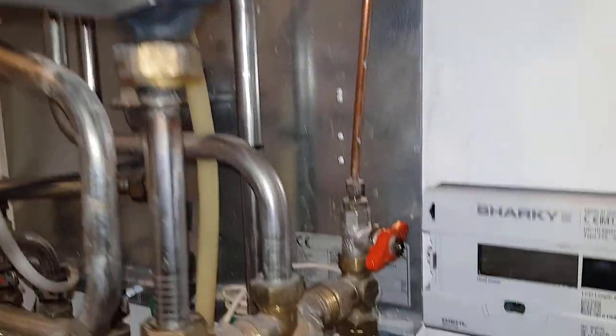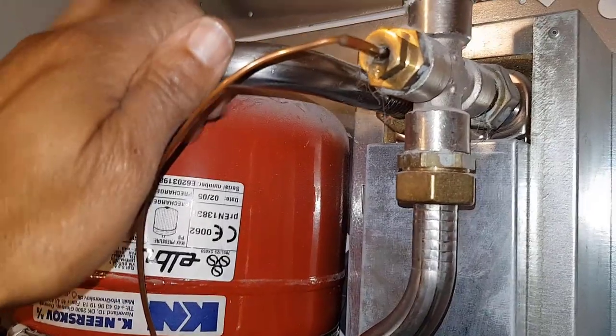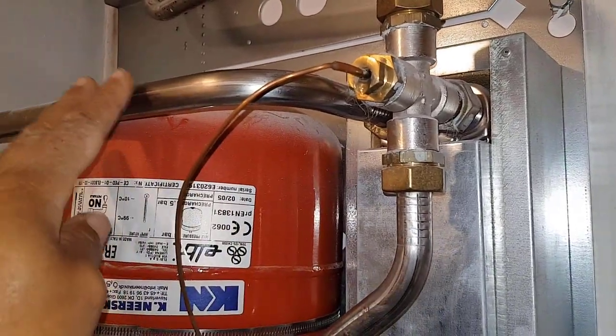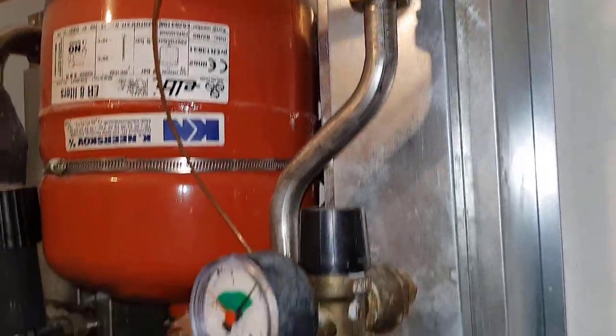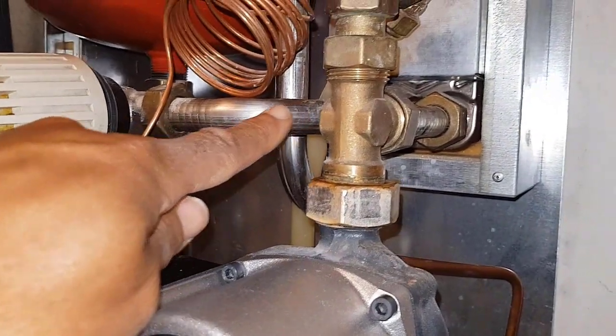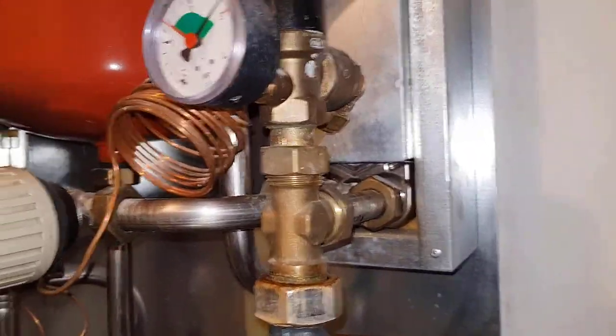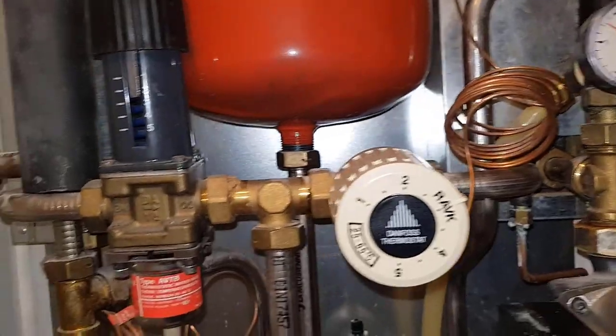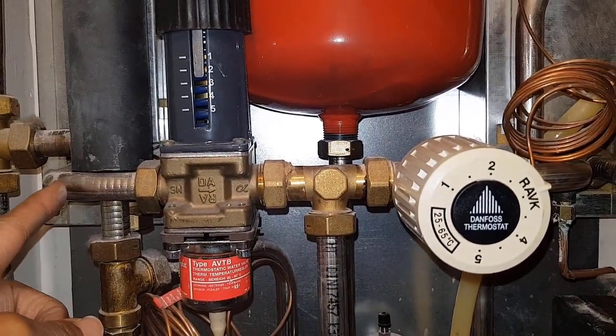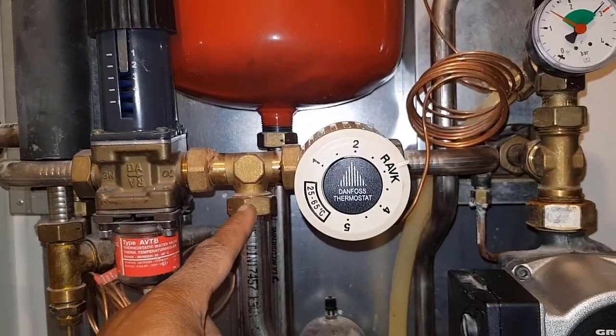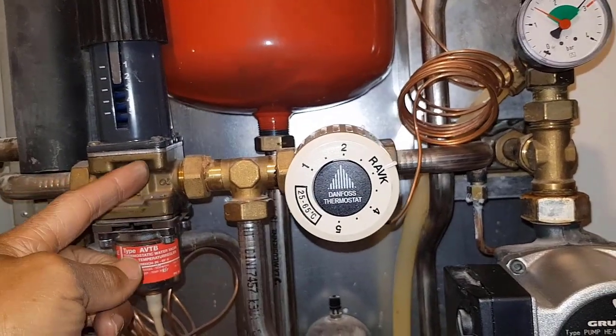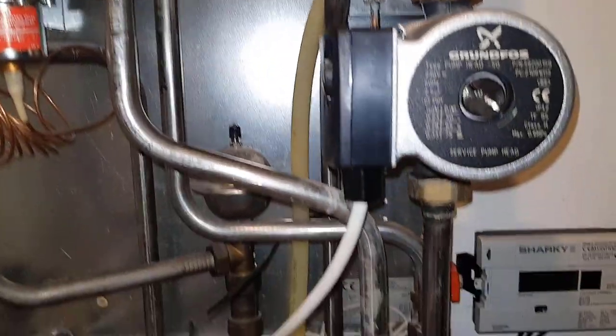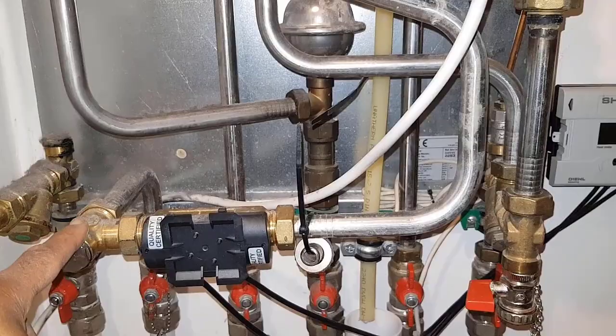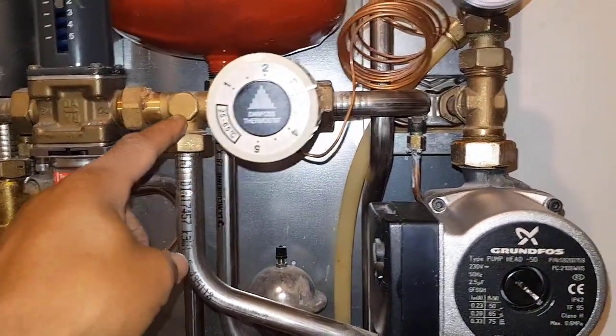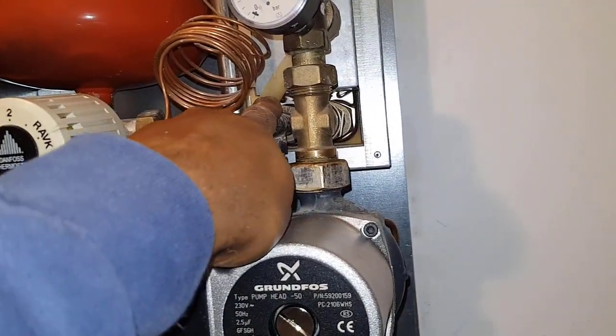What I've done now is open this bypass valve here, and what we've now got is this has got really hot. That's a flow going in, because that wasn't so hot before, but now it's gone a lot hotter. However, we're still not getting any flow through here on the return going back to the communal return. Now what's happening, this is the return also from the plate heat exchanger going back. So this is like the common return, this T-piece. It's flowing this way through this valve and down through here, going back to the communal return. However, this way, coming back from this plate heat exchanger, is cold.